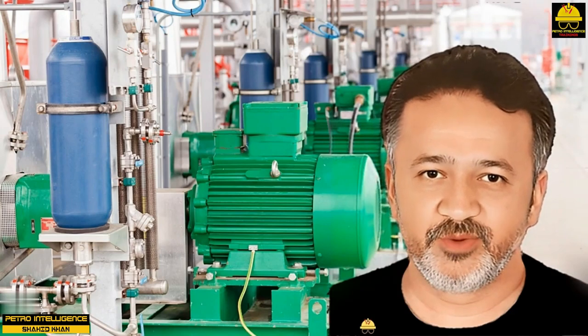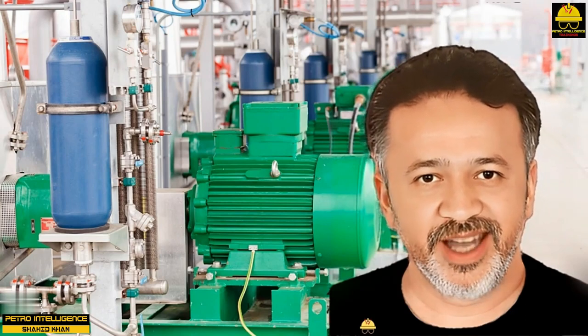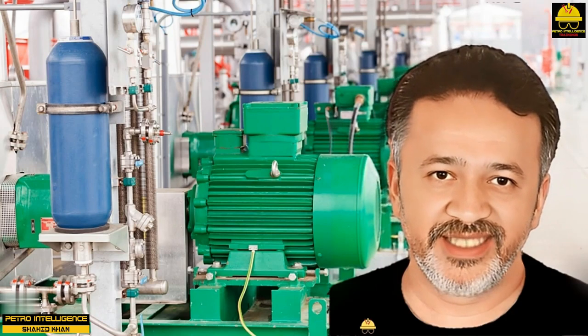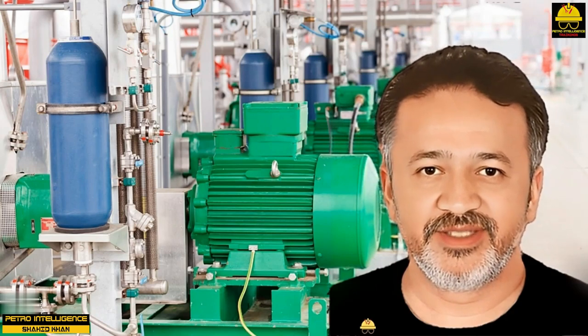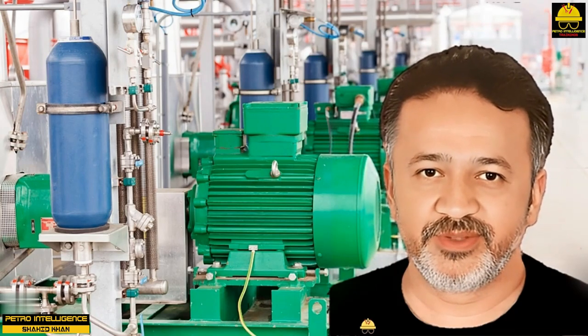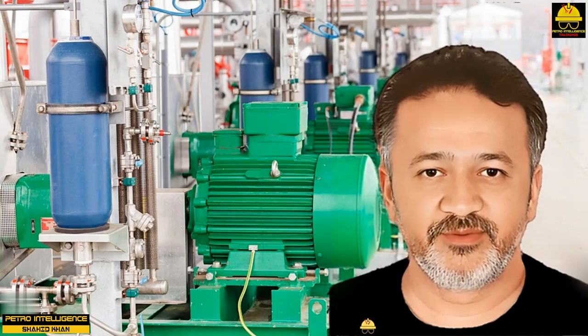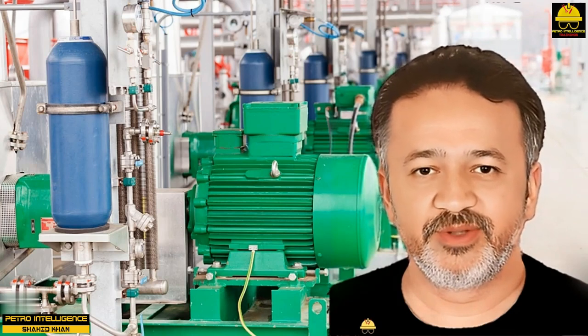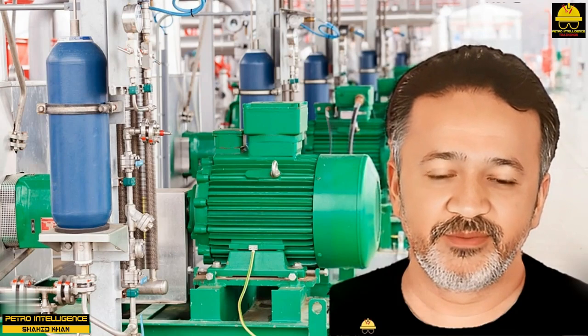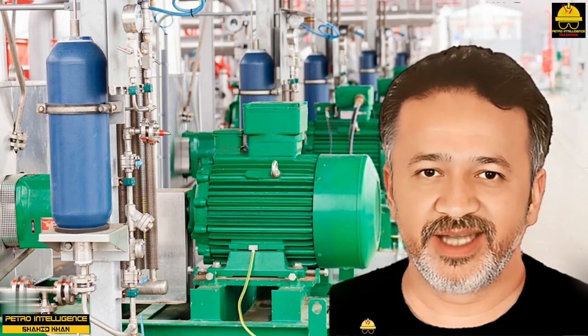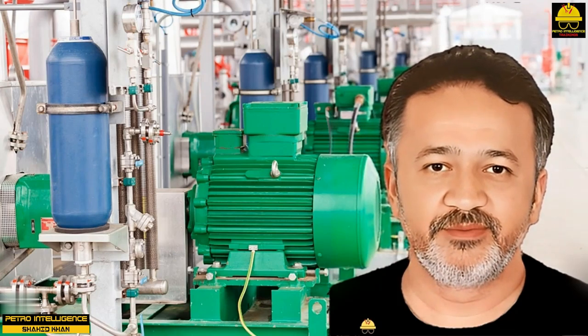The suction line of a reciprocating pump should be as short as possible. Excessive valves, bends, and fittings should be eliminated. The line should be large enough to deliver fluid velocities of 3 feet per second. Booster pumps typically can be added to the suction line to increase suction pressure.